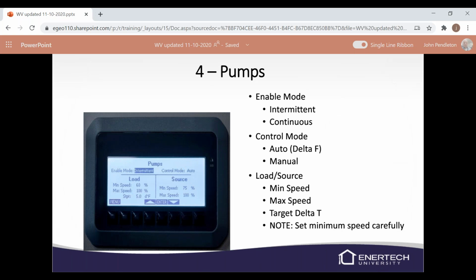Here's where, if you need to run your pumps to check them out, you can put them in continuous and your control mode in manual. And then it'll run your pumps at this all the time. You don't want to leave it in that mode. I guess you could if you really wanted to, but I wouldn't recommend it. But if you need to test things out, then you can put it in manual mode and run those pumps.